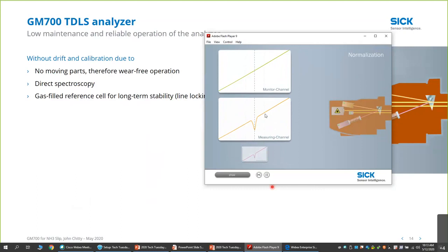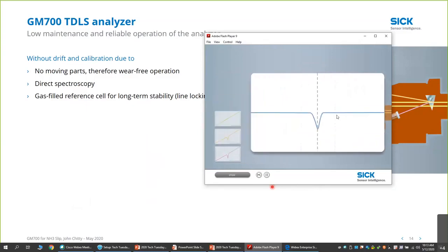This shows the absorption peak. See that here. And then we use a curve fit. So we take one curve, we look, it doesn't fit. We take another one, we actually see that's ammonia. And then we keep trying curves until we see one that fits, and that gives us a value. In this case, it's 1.77 ppm.